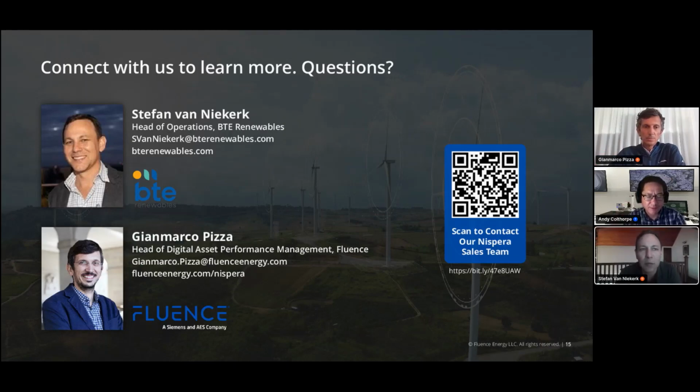Yeah, I would say if you approach it generally, first it's understanding our energy availability of each of the plants and on platform level. You want that view, and you've got various contracts to work with that have got different metrics. So to get that view established is really important, and then to be able to allocate energy losses to collective problems has really been important in our case. And there, for instance, on our solars, we've had our biggest losses coming from inverter clipping, sometimes in summer months. And this is now during a defect notification period, I must also say that.